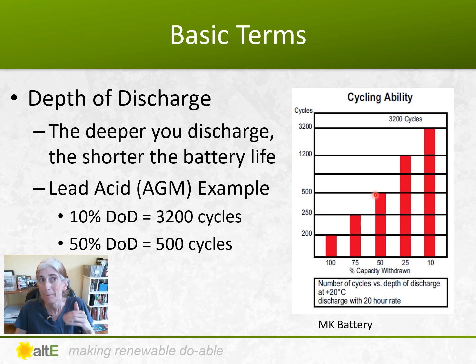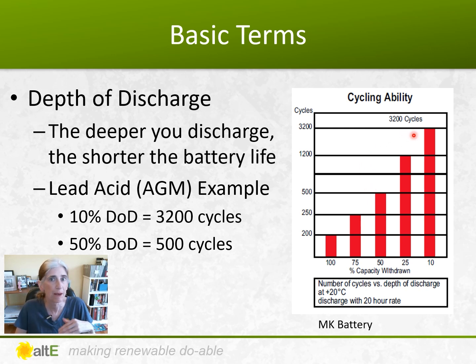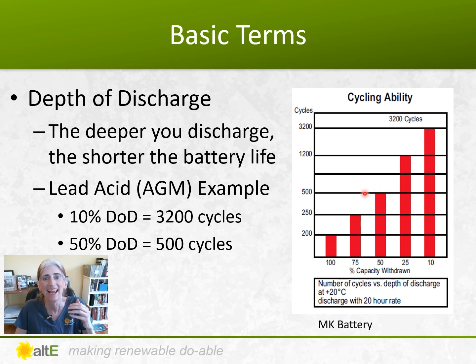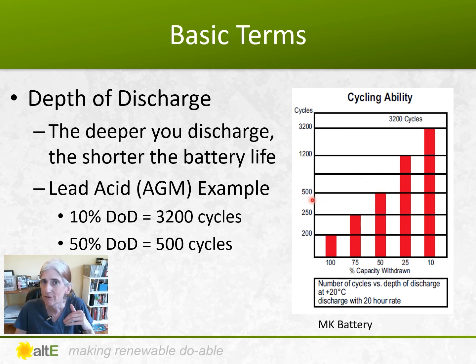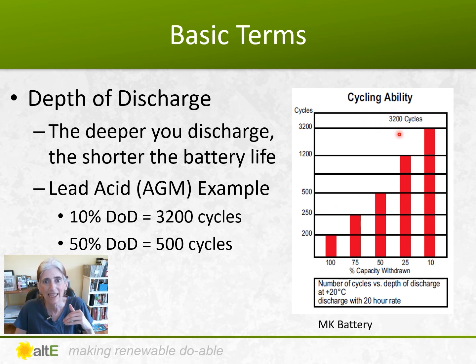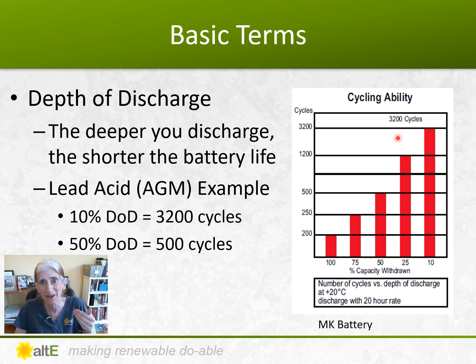That 50% figure is after multiple days — worst case, no sun for a couple of days. You might use 25% one day and another 25% the next day, then the sun comes out. You don't want to design your system to use 50% every day, because you'll only get 500 cycles out of it — less than two years — as opposed to 3,200 cycles if you use it lightly. The downside of doing too light a depth of discharge is that you'll need a bigger battery bank.